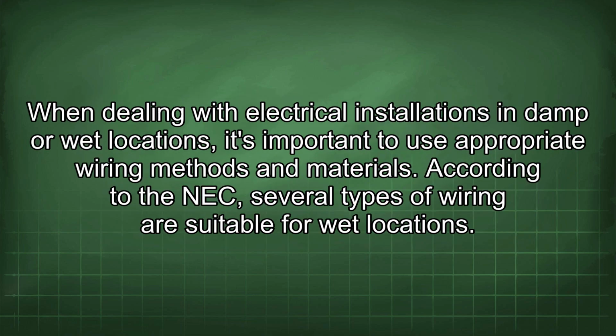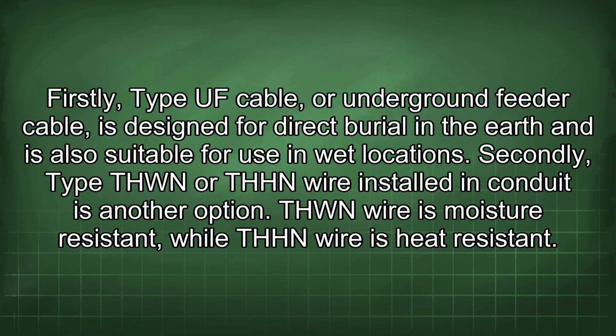When dealing with electrical installations in damp or wet locations, it's important to use appropriate wiring methods and materials. According to the NEC, several types of wiring are suitable for wet locations. Firstly, type UF cable, or underground feeder cable, is designed for direct burial in the earth and is also suitable for use in wet locations.